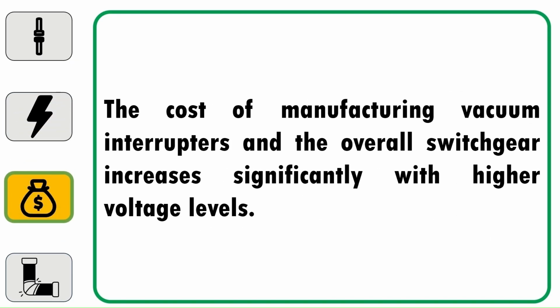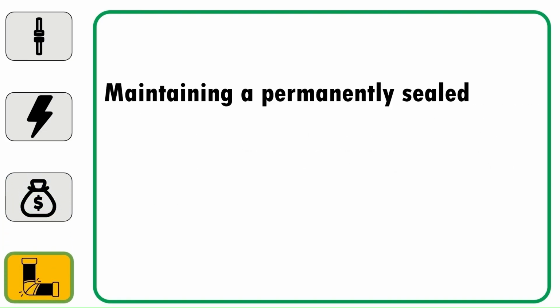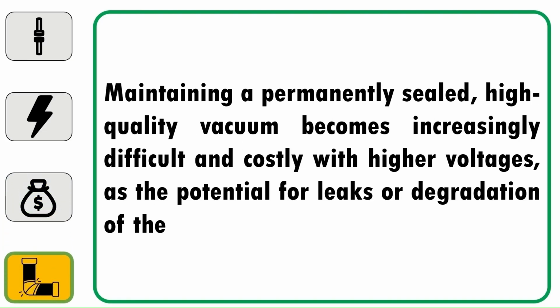The cost of manufacturing vacuum interrupters and the overall switchgear increases significantly with higher voltage levels. For high voltage applications, technologies like SF6 filled circuit breakers become more economical and practical. Maintaining a permanently sealed, high-quality vacuum becomes increasingly difficult and costly with higher voltages, as the potential for leaks or degradation of the vacuum increases.